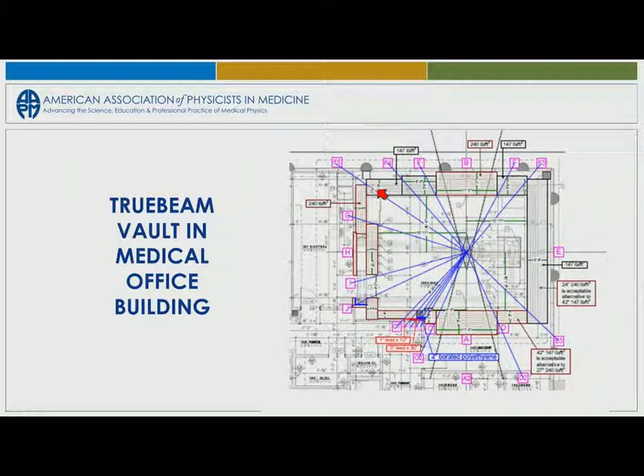So what we wind up giving them is all these different increments. And notice this is your 240 pounds per cubic foot of concrete. Going with high density concrete is still cheaper than going with lead, if they can get it. What I recommend, if you've got to go with one of these sections, is high density concrete; look at manufacturers that'll give it to you in blocks. It's like constructing Legos. They precast them, they control the density, so you know you're getting what you specify, and they just layer them up. It's literally like constructing Legos, but it works really well, and you know it's actually the specified density.